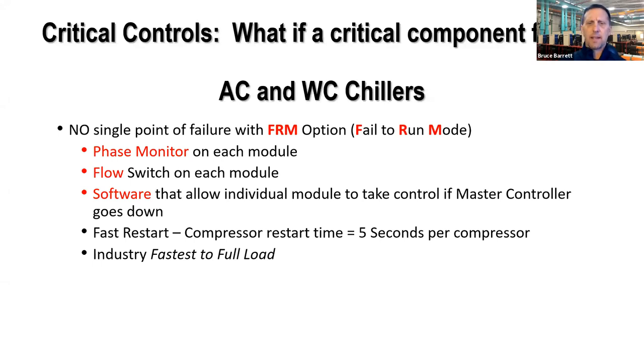Certainly there can be things taken on in the design of your system, where adding large buffer tanks, slowing the loop volume down, along with the fast restart time is going to give you a very stable system. Again, very low cost option. Phase monitors are cheap. Flow switches are cheap. The software is already written. It's a very low cost, high value add.